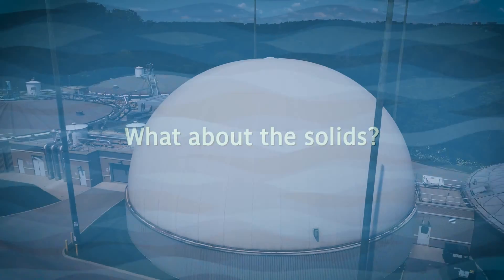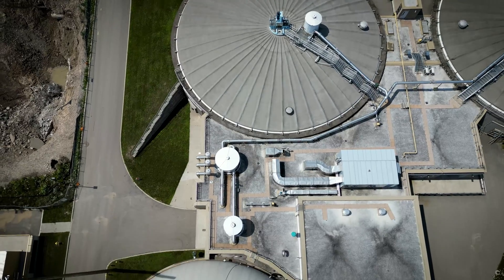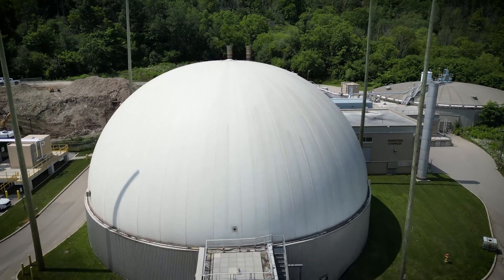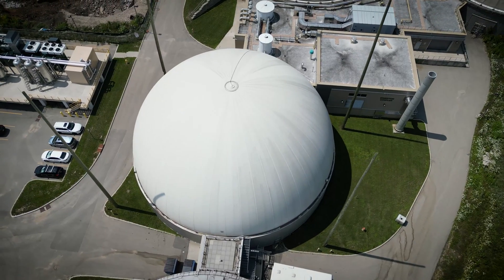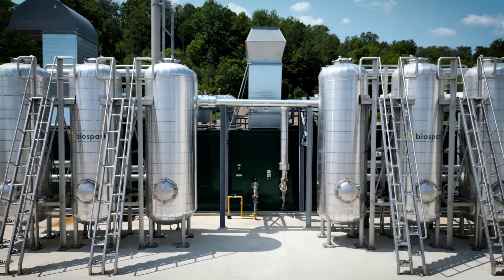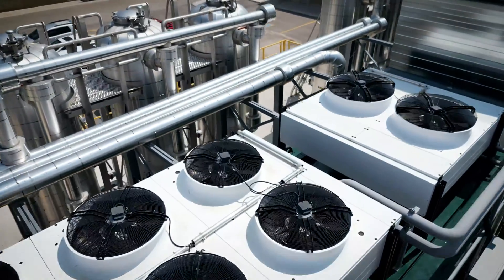What about the solids? After the solids leave the primary clarifiers, they enter the digesters. We pump the solids into digesters, where another group of tiny, microscopic bugs get to work. These bugs do not like oxygen, so instead, we force all the air out of the tanks. While the bugs are eating the organic matter, they produce methane and carbon dioxide — two harmful greenhouse gases. The Kitchener Plant uses technology to capture and convert the gases to produce green energy, and this renewable energy helps to operate and heat the plant.